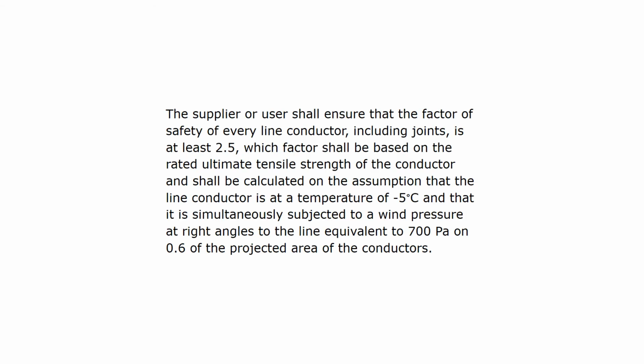Conductors. The supplier or user shall ensure that the factor of safety of every line conductor, including joints, is at least 2.5, which factor shall be based on the rated ultimate tensile strength of the conductor and shall be calculated on the assumption that the line conductor is at a temperature of -5 degrees Celsius and that it is simultaneously subjected to a wind pressure at right angles to the line equivalent to 700 Pascal on 0.6 of the projected area of the conductor.